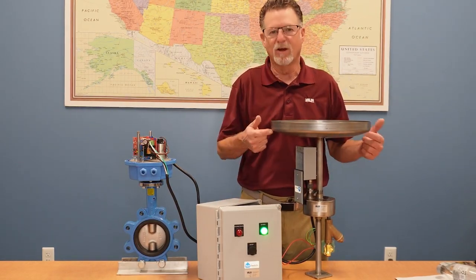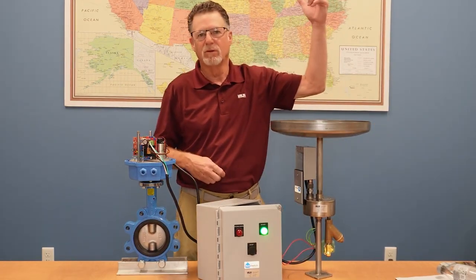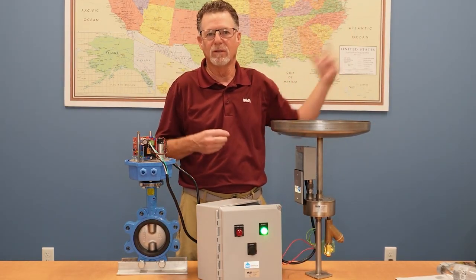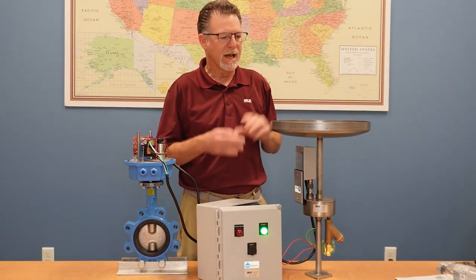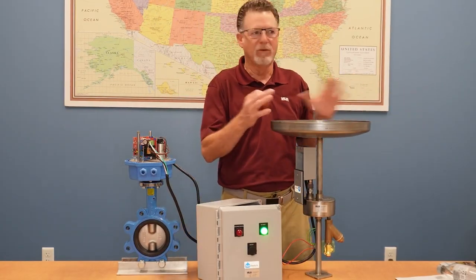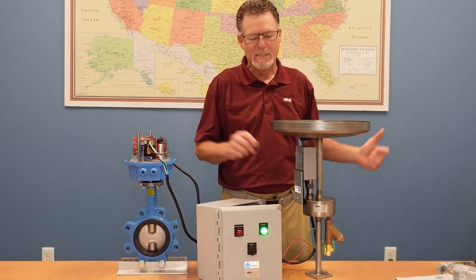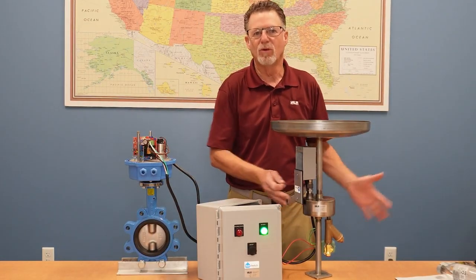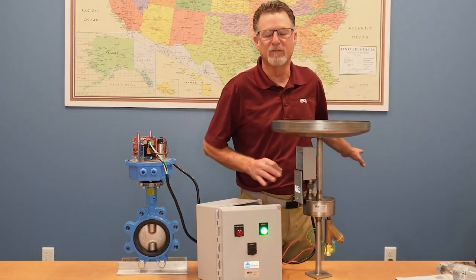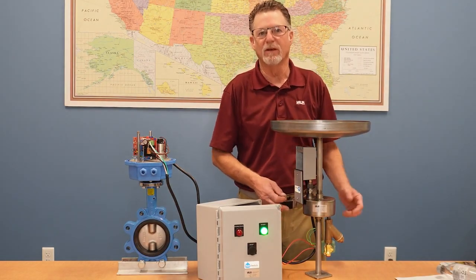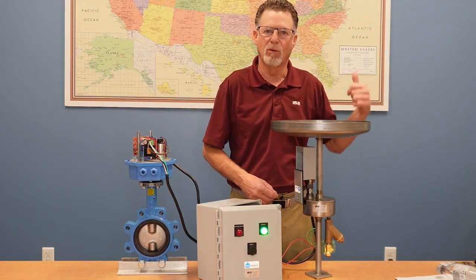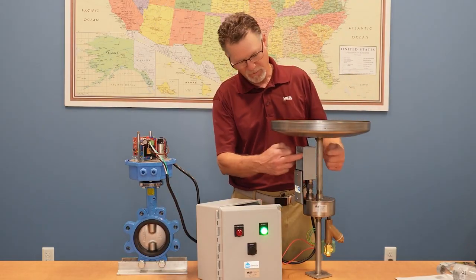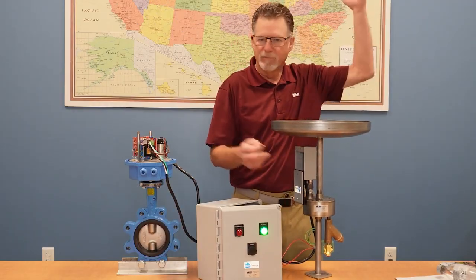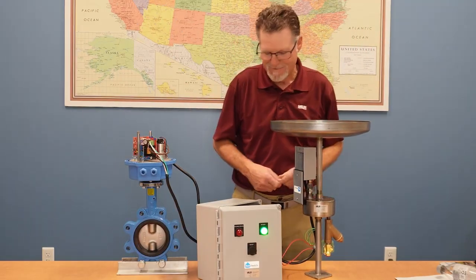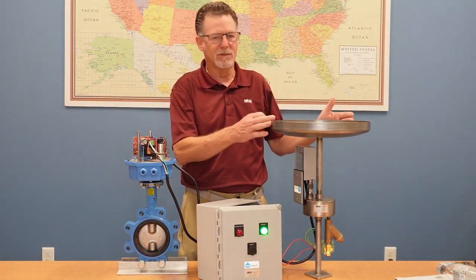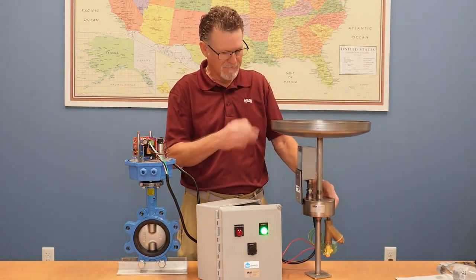This funnel would normally be installed on the top of a building or a flagpole or any kind of a pole. It's got to be where rain can get to it from any angle, with no obstructions. And then the rain switch would normally be at grade. It's best if it's installed at grade so you can do the servicing of it, not have to go up on a roof or up a pole to do the servicing. So this plumbing can be 30 feet, it doesn't matter, as long as the rain that gets captured here gets to this chamber.